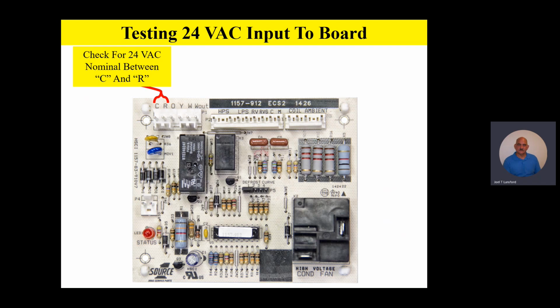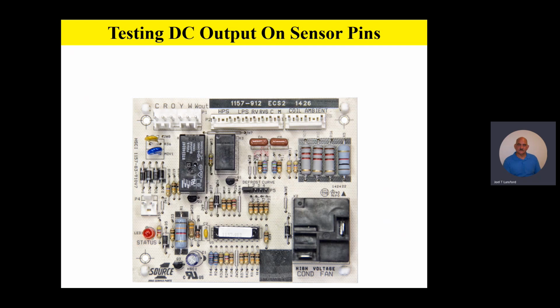So as long as you've got 24 volts on the board, the next step will be to find out if we have the DC output on the board that's necessary for the sensors. So once we've confirmed that we have 24 volt input to the board between C and R, the next thing we want to do is remove the coil and the ambient sensor from the board. Let me say that one more time. We're going to remove the sensors from the board, just unplug them from the board where it says coil and ambient. And then we're going to take our voltmeter and we're going to be looking for 4 to 5 volt DC on the pins where the sensors actually plug onto the board.